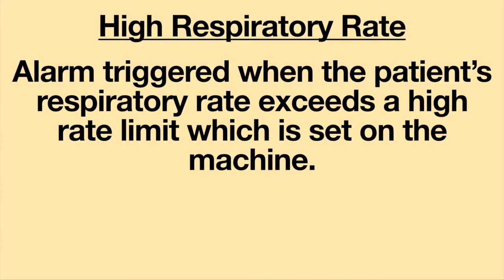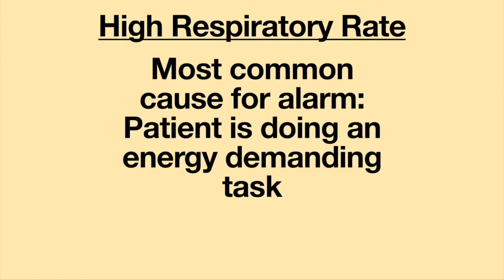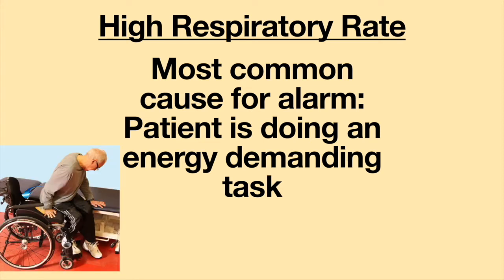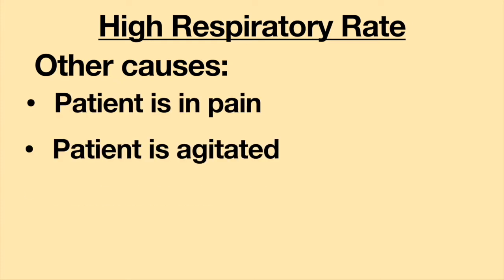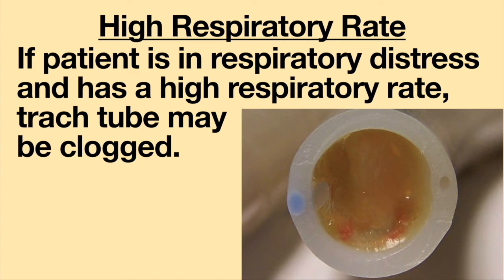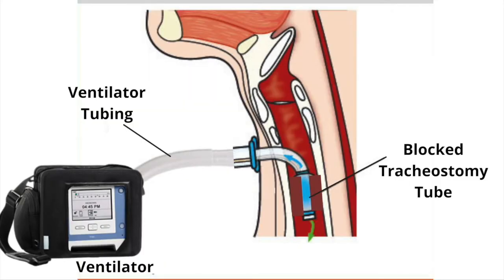A high respiratory rate alarm is triggered when the patient's respiratory rate exceeds a high rate limit set on the machine. The most common cause is the patient performing an energy-demanding task such as transferring into or out of a wheelchair or lifting a heavy object. Other causes include pain, agitation, or fatigue. If the patient is in respiratory distress, the tracheostomy tube may be clogged with mucus, delivering little air to the lungs, causing the patient to breathe faster to compensate.